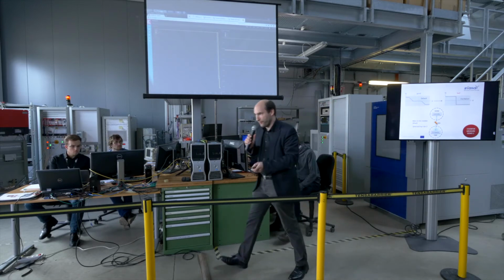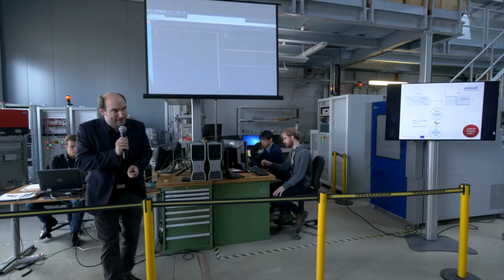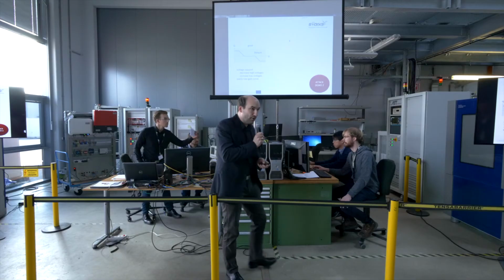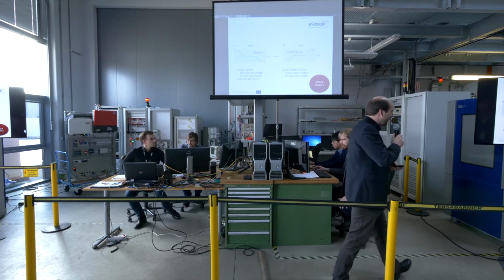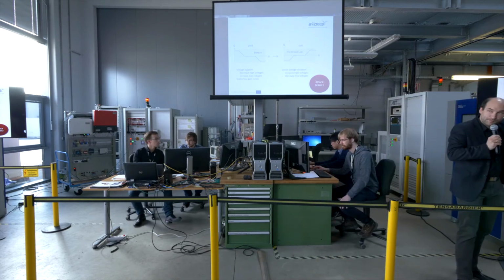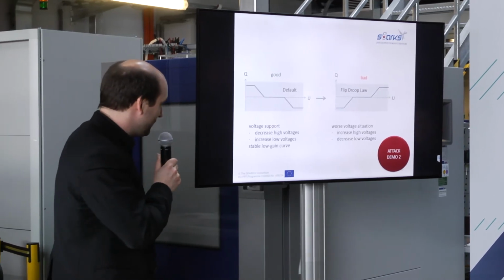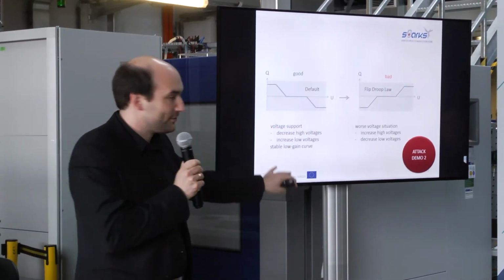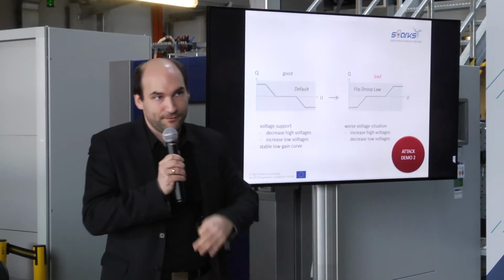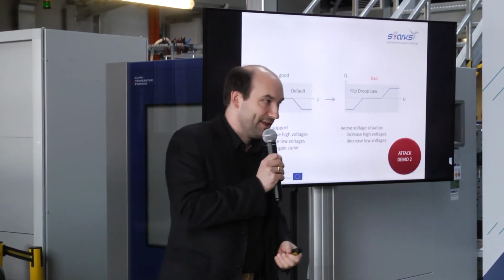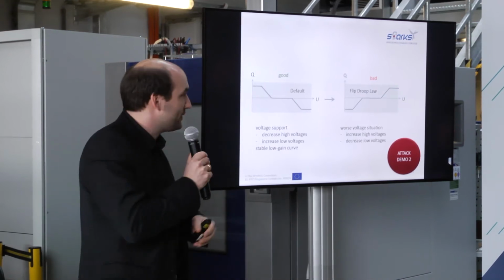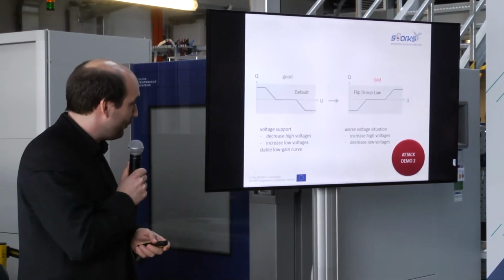As we've heard in the symposium, there are many potential attacks, so we could show you all day different versions. We decided to take one more go and play with this reactive power curve. This time we're not increasing the gain, but flipping the curve, so instead of supporting the voltage, it will worsen the situation. If we have a high voltage at the connection point, reactive power will be fed in, which increases the voltage even further.